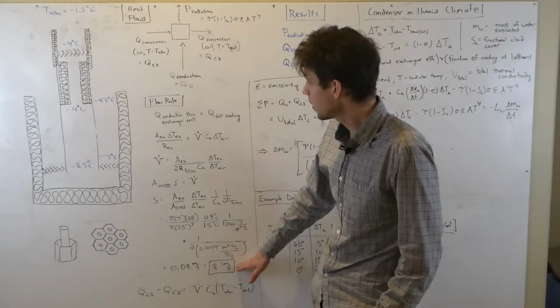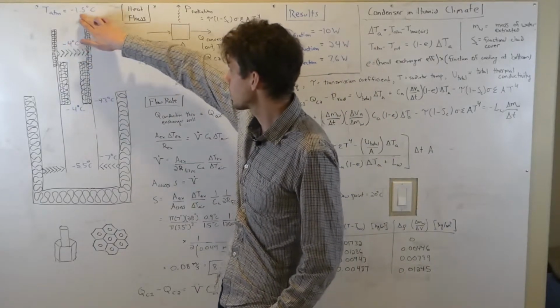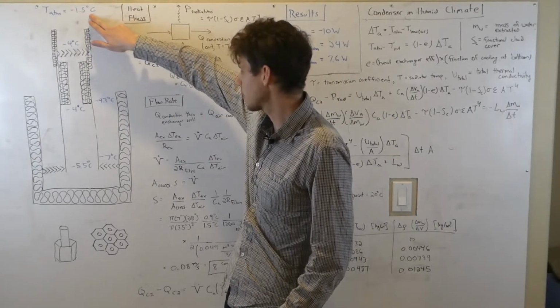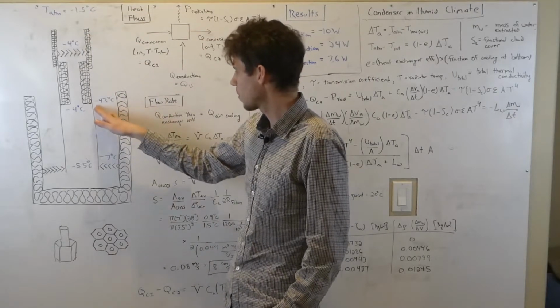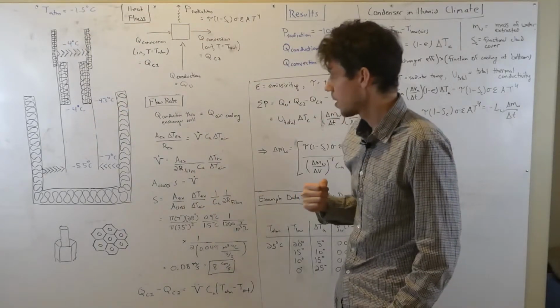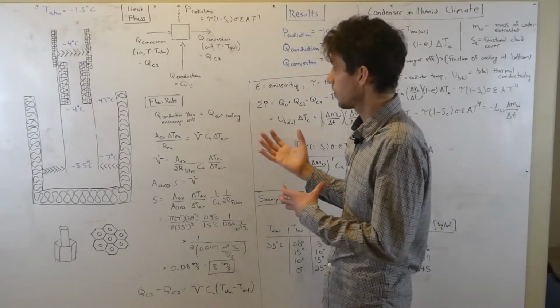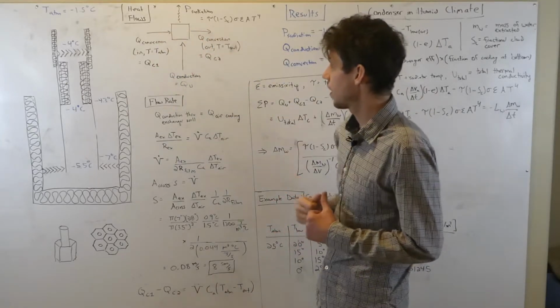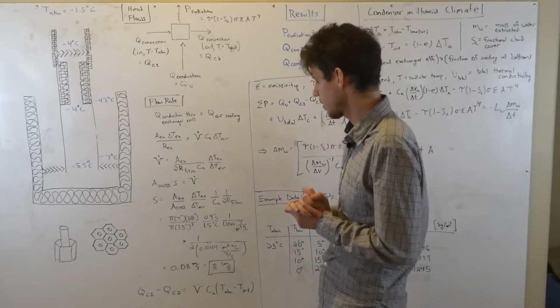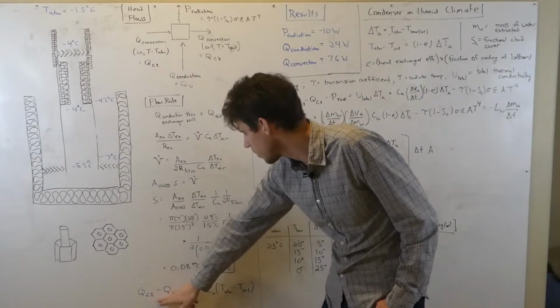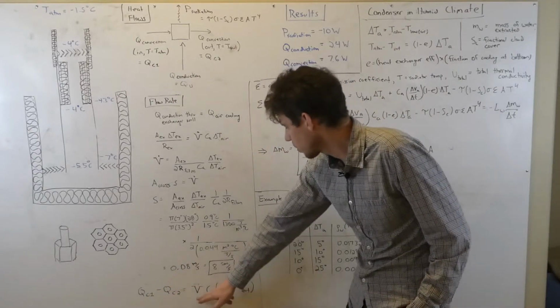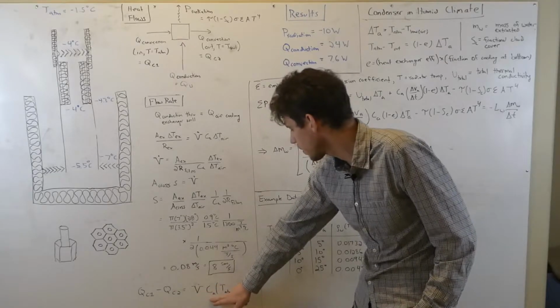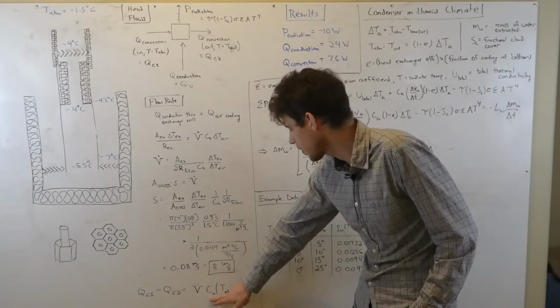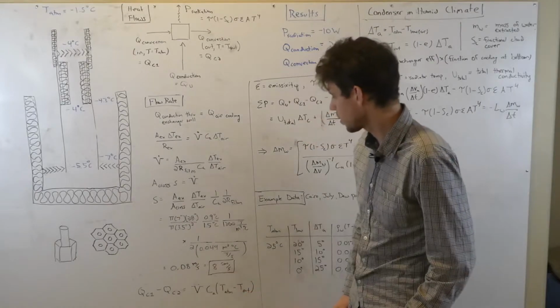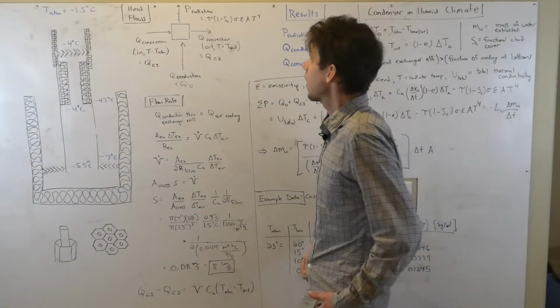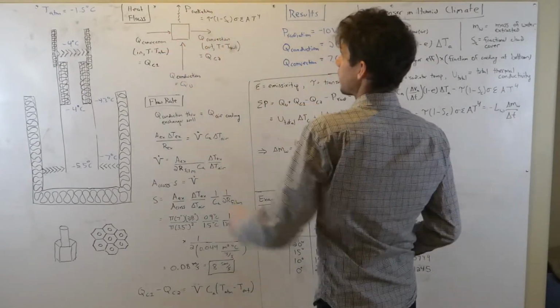Now that you have the airspeed and the temperature of the incoming air, negative 1.5 degrees Celsius, and the outgoing air, negative 4.3 degrees Celsius, you can solve for the net convection power. That's QC1 minus QC2, equal to the volumetric flow rate times the volumetric heat capacity times the difference in temperatures. Then from the energy balance, you can figure out everything else.